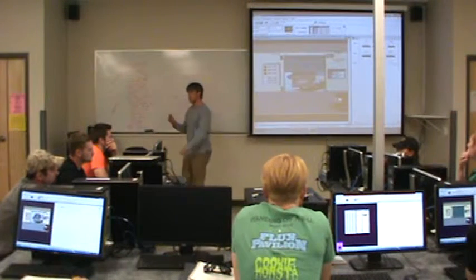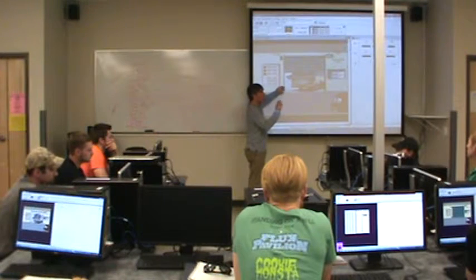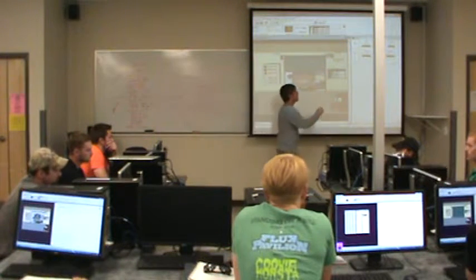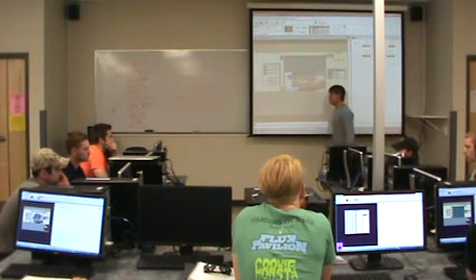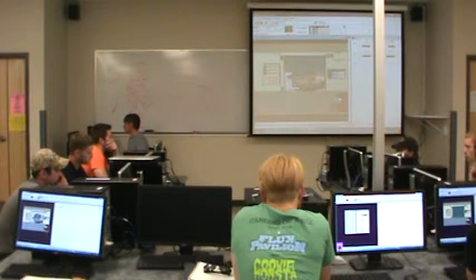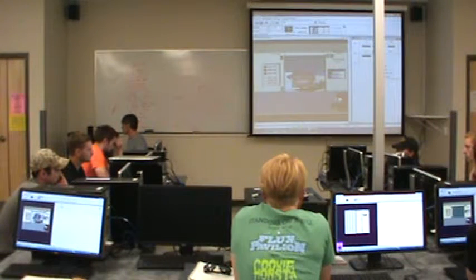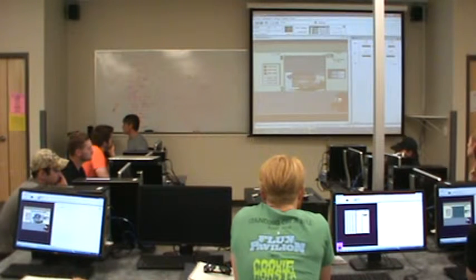So what you have to do is invert, okay? Right now, I'm getting a 0 from this in memory. What I want to get is a 1. So I need to invert it in this command, which means I need to use the opposite command here. Okay, so let's try that. Program, lower limit, right click, change to examine if open, download, run.